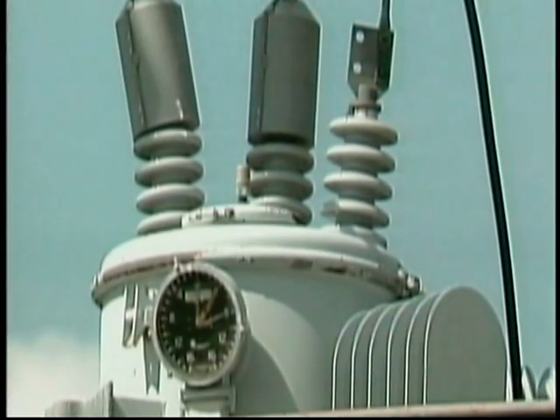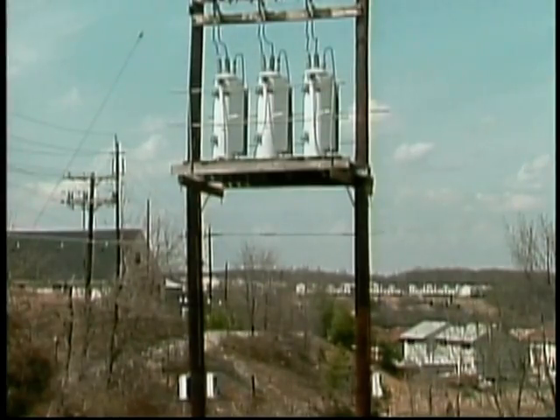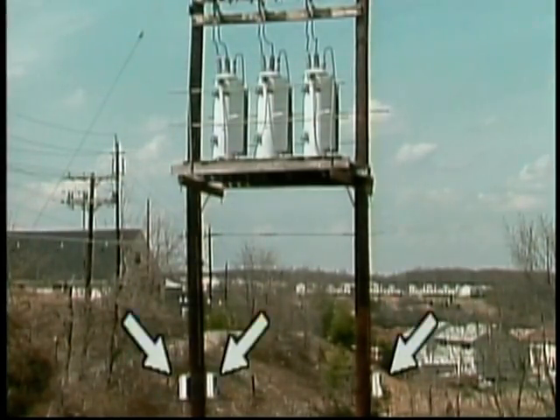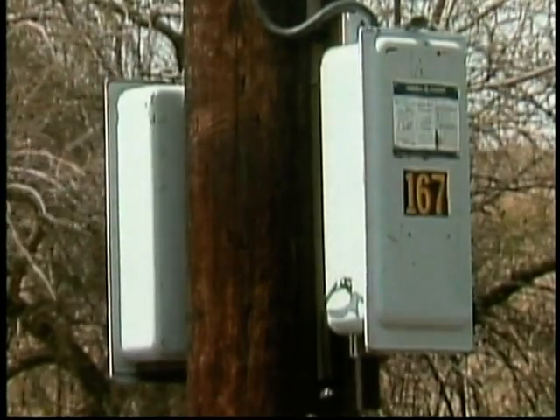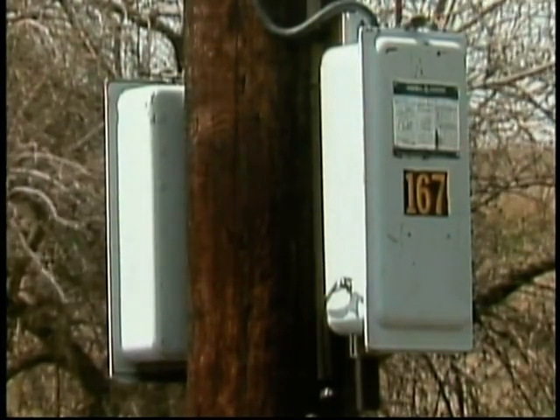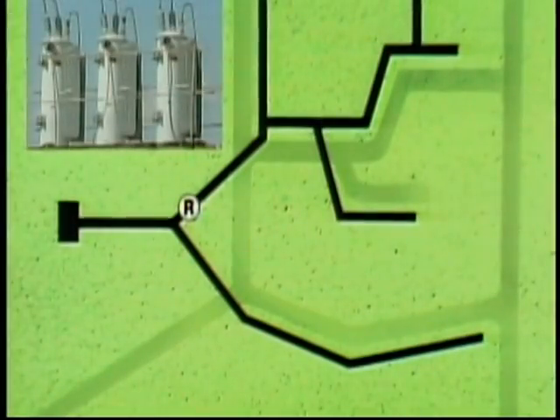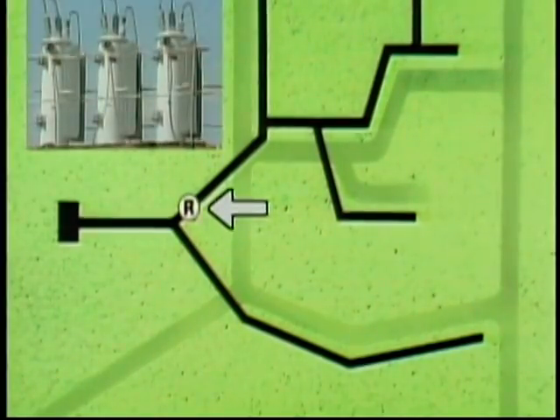A second identifying feature is a position indicator. Voltage regulators adjust voltage by moving a coil or by changing tap connections to a coil. The position indicator indicates the present coil or tap position. A third identifying feature is a control box on the side of the regulator tank or on the utility pole near the ground below the regulator. The controls are used to set the operating values of the regulator. Like distribution transformers, voltage regulators may be found anywhere on a distribution primary.